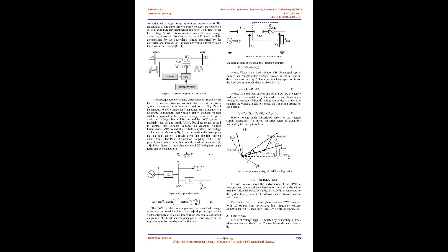This model of DVR is based on the principle of operation of power electronics such as the IGBT, and its intervening of compensation through relays using bypass switches. In normal conditions, the IGBT switch is off and the control system transfers the power to the load through the thyristor bypass switch. When voltage disturbance occurs, the control system compensator makes the thyristor turn off and commands the IGBT to turn on, and power flows through the IGBT and auto transformer. Utilizing the auto transformer and the IGBT improves the output voltage, maintains constant in both PWM and voltage controls.